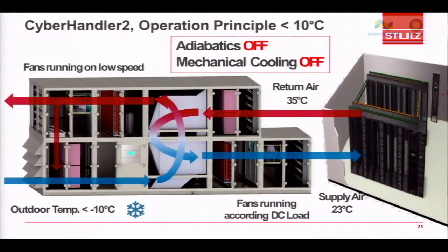Here is the thing when adiabatics off, mechanical cooling off. You can see actually when the outdoor temperature is less than minus 10 degrees Celsius, which is very difficult in India, but the modes are available when temperature falls below minus 10 degrees Celsius. So you don't have to run your compressor, only the fans are on and fans are cooling the data center.